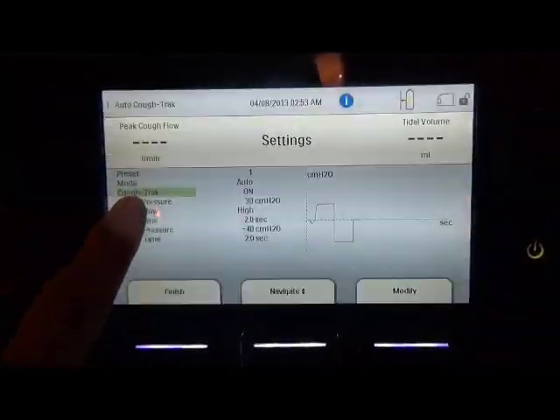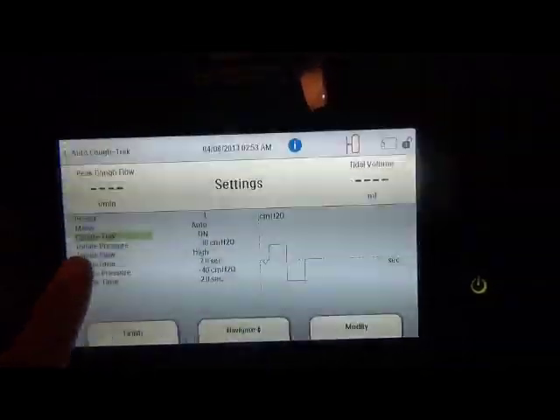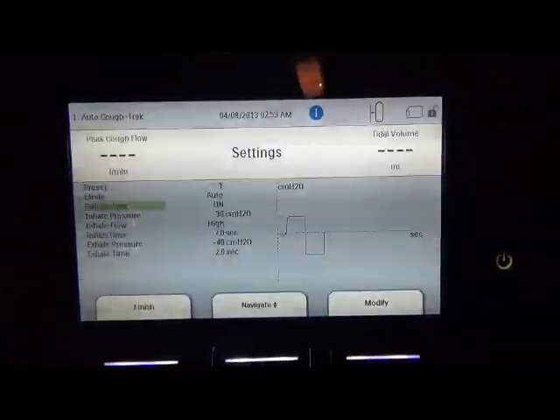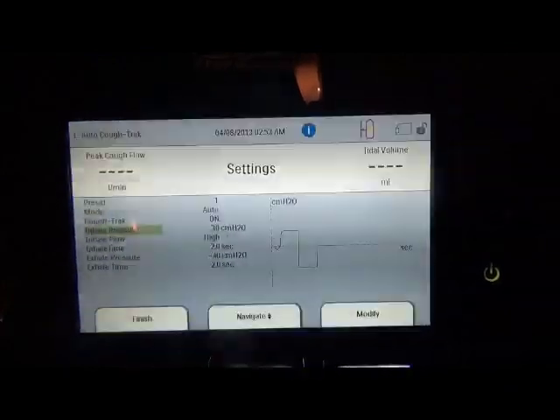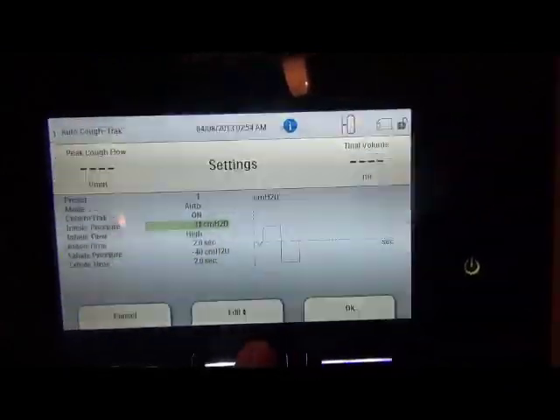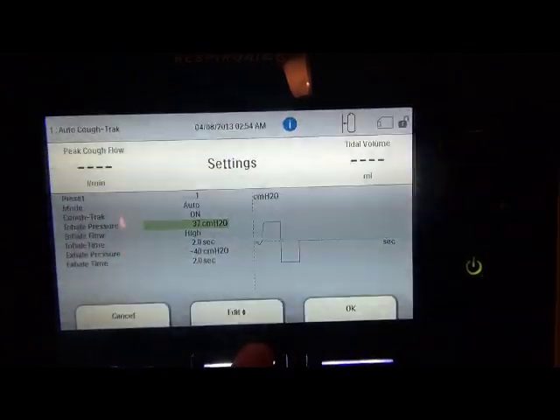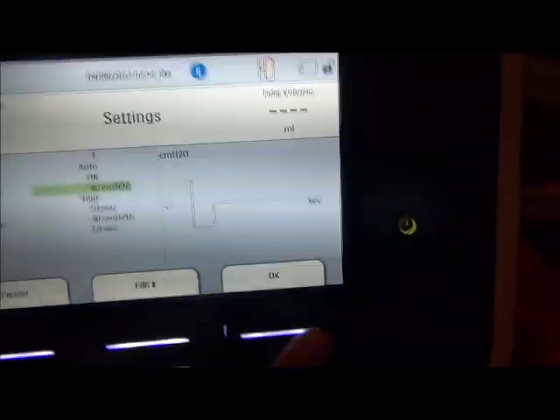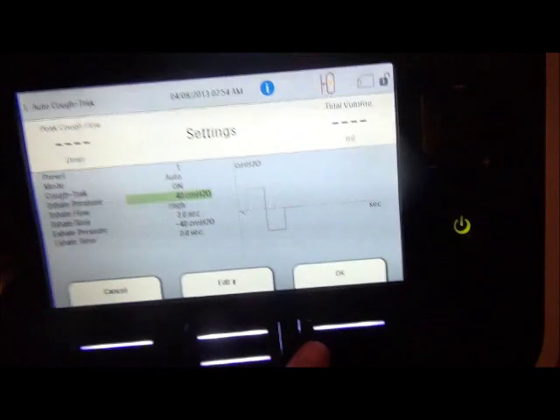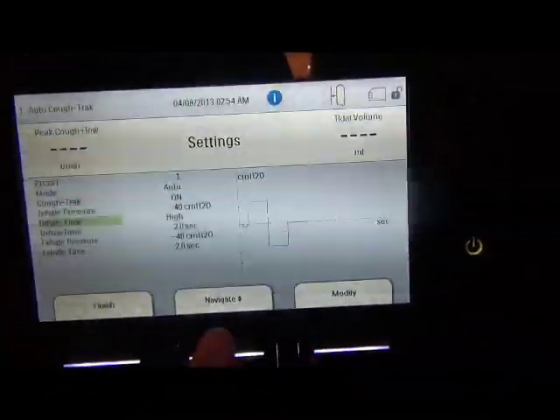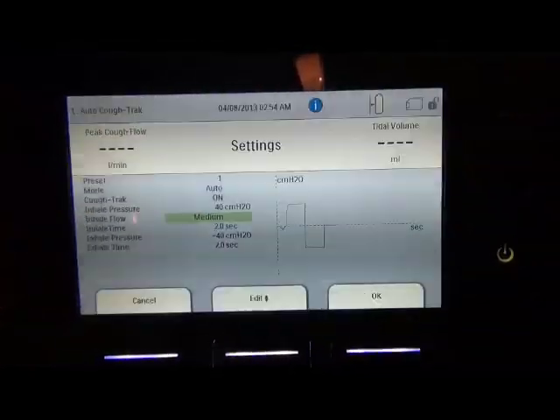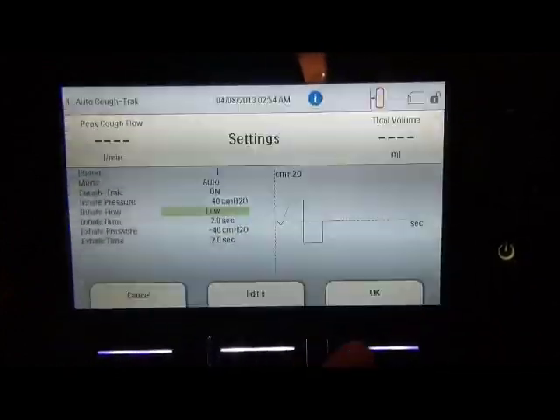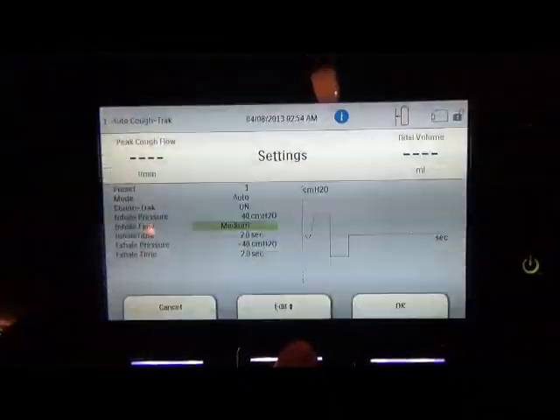Then the highlighted portion of the menu shifts. The Cough-Trak, we'll go into that in a moment. We're going to come down and change the inhale pressure. We can increase or decrease this. I'm going to go up to 40. I'm going to say OK. And then I have 3 options for inhale flow. I'm going to modify, and I'm going to come back over here, and I got high, medium, and low. I'm going to say I want to keep it on high and confirm.